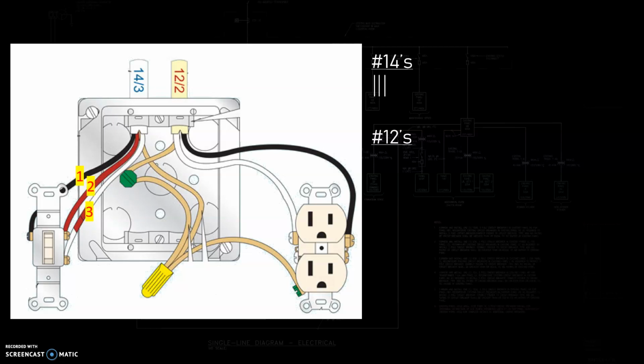Good. Now let's go ahead and actually count our switch. Since those 14 gauges are connected to the switch, let's go ahead and count that guy. So we have a double volume allowance, right? So there's 4 and 5 based on the largest conductor connected to it. Okay. I'm not going to count this 14 ground because remember for the grounds we only count the largest ground in the box, and we actually have some number 12s in there. So we're not going to count the 14s at this point. So I think we've got all of our 14 wires counted. So jumping on to 12, let's count the conductors that originate outside the box, not including grounds. We have 1, we have 2.